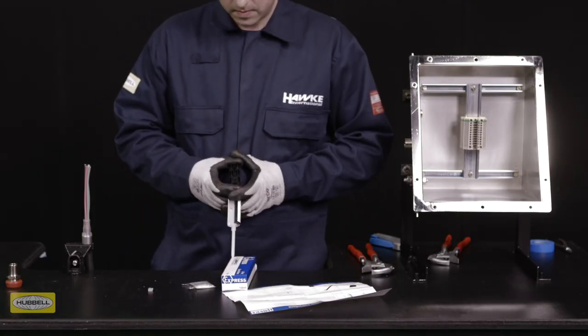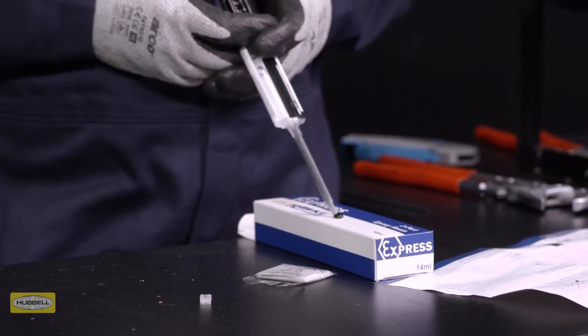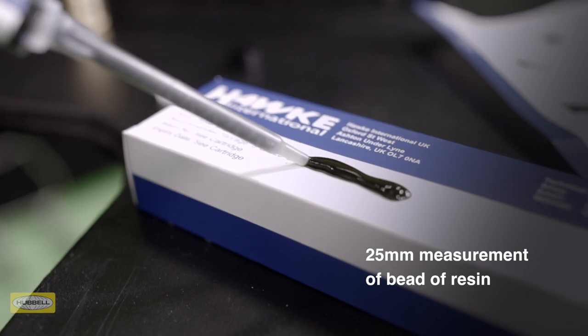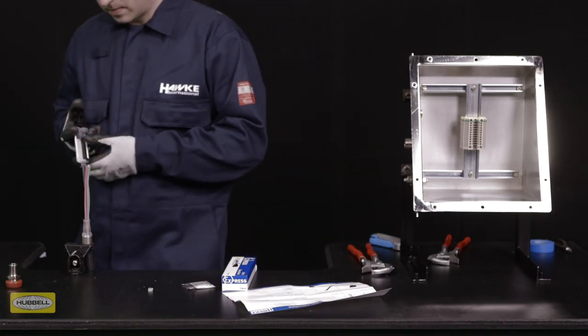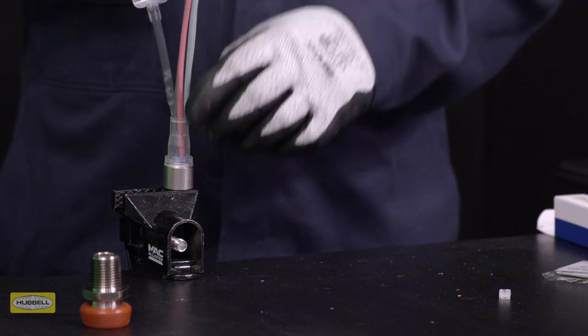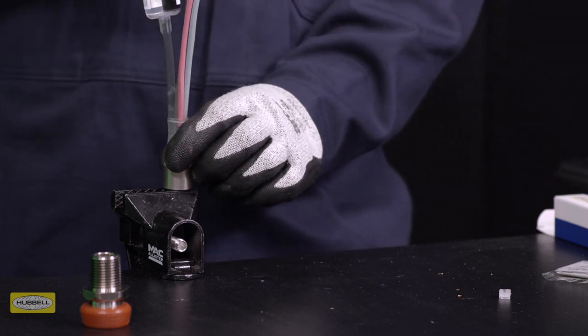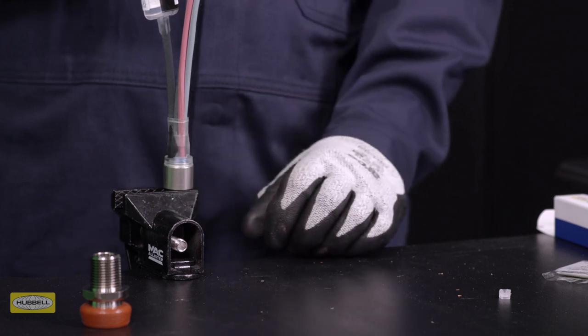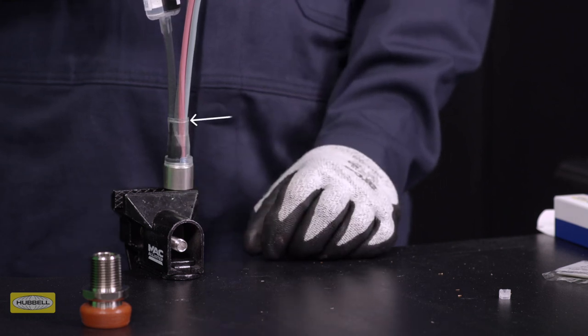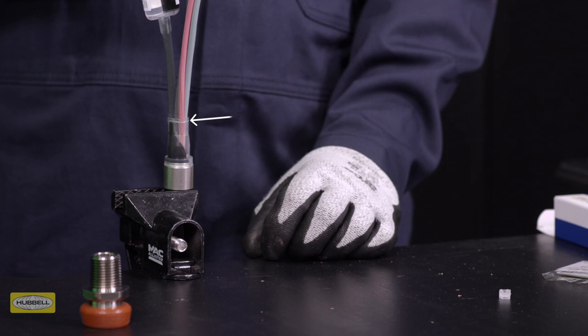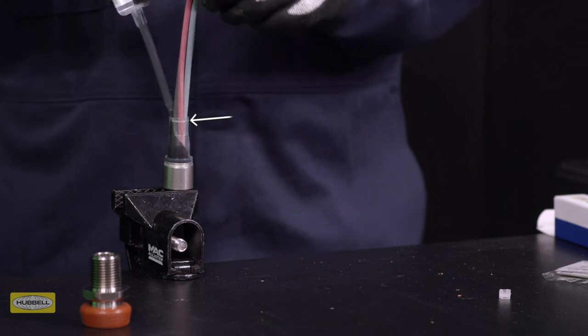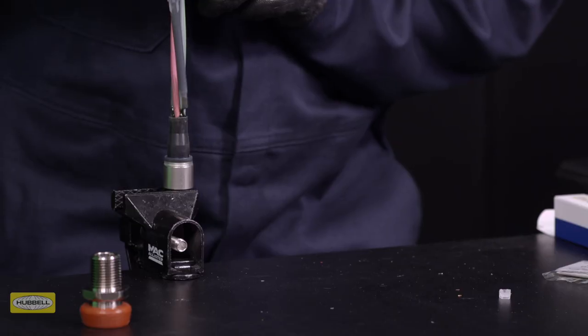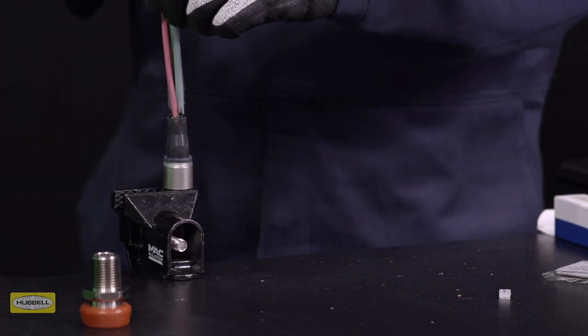Purge approximately 25 millimeters or one inch of resin onto a disposable surface to ensure that the resin is properly mixed. Ensure the gland is held vertically with the nozzle starting as far down the pot as possible. Fill the resin to approximately three millimeters under flush. This is indicated on the silicone pot by the fill line shown on screen. Check that the resin is properly filled without any voids.